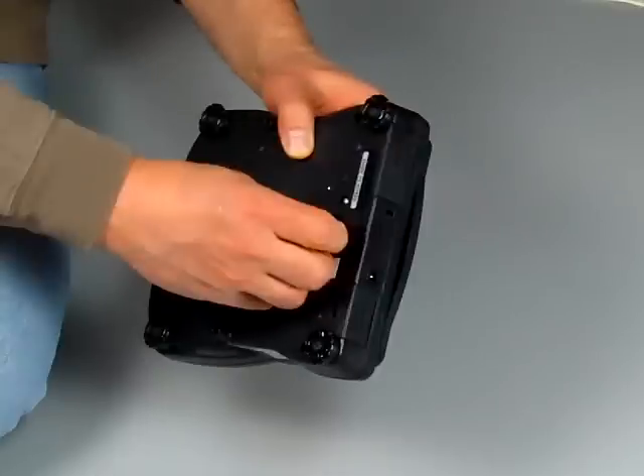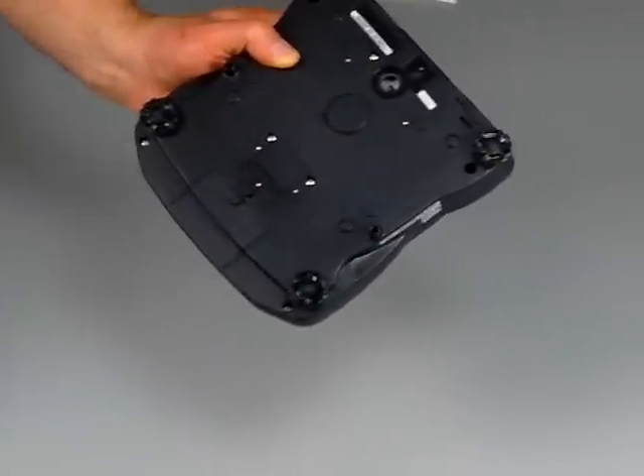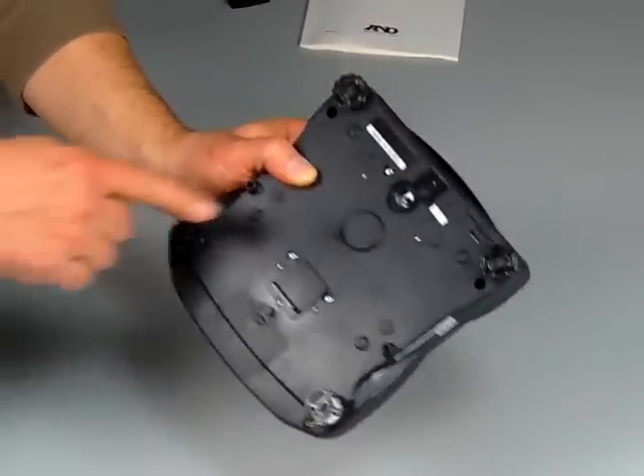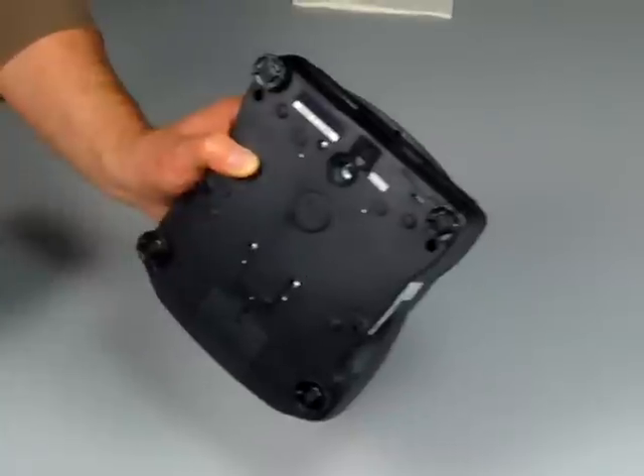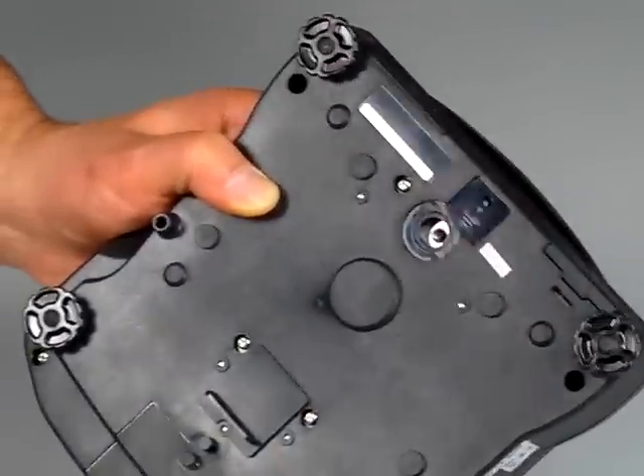There's an underhook — on some of the models of the EJ series, and I'll discuss this later, there is the underhook feature. This is the 4100 that I have, so you can see the underhook port here. You have to buy an I-hook, which is an accessory from A&D, and it enables you to weigh magnetic material or hot items. That's a real nice feature for this price category.